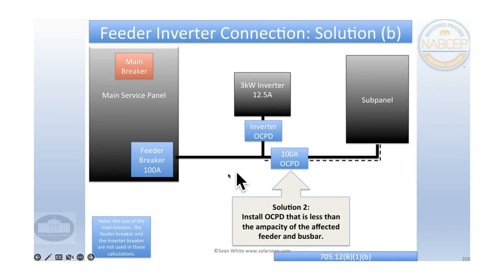So what they say now is that as long as it's within 25 feet of this connection point, it would comply with the 25-foot tap rule. So if this sub panel is within 25 feet of that connection point, then a breaker at the sub panel would work. So pretty much what it's saying is this overcurrent protection device has to be within 25 feet of that connection point, but still there are people that will interpret it where you can have it go as far as you want, put it at the sub panel, and that's for in buildings, the 25-foot tap rule. So if you're outside, you can go as far as you want.